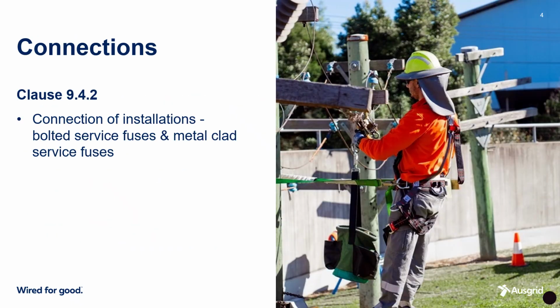In Clause 9.4.2, regarding the connection of customer installations to the low voltage network, bolted service fuses and metal-clad service fuses have now been included along with barge board mounted fuses in the situations where the customer main switch or switches may form the point of isolation instead of the service fuse.